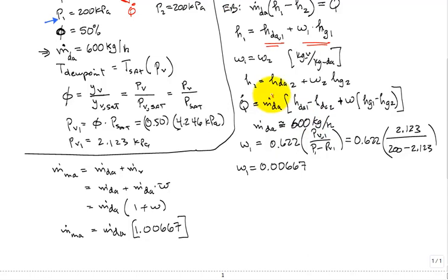So we're going to say that this is 600 kilograms per hour. How about this change in the enthalpy of the dry air? We'll replace that by the specific heat of the dry air times the temperature 1 minus the temperature 2. What is this specific heat of the dry air? That's 1.005. Everybody uses that. It's kilojoules per kilogram Kelvin. And you had a temperature change. It came in at 30, went out at 20. That's a 10 degree Kelvin change or 10 degree C temperature change.